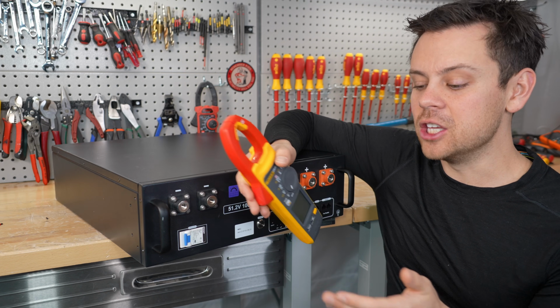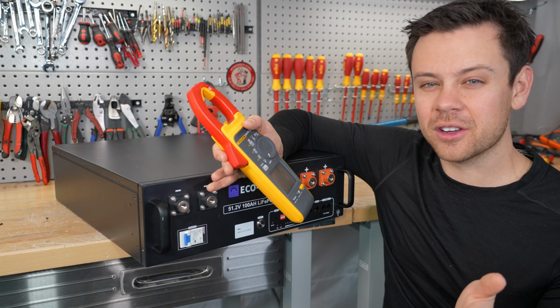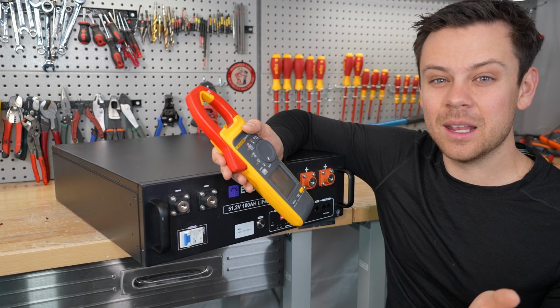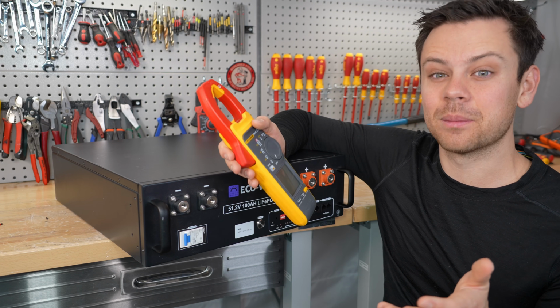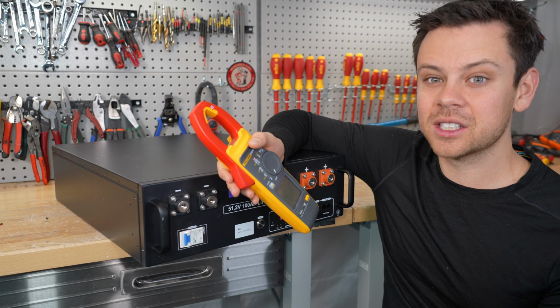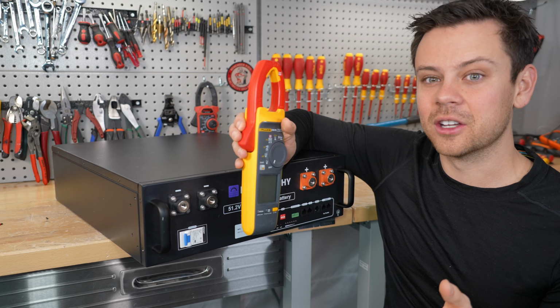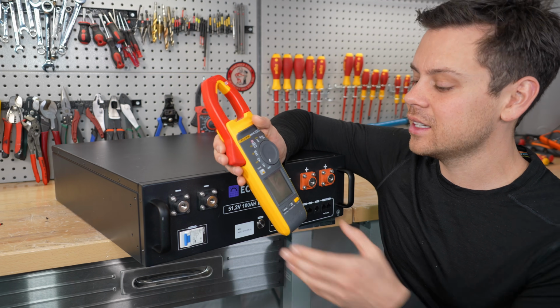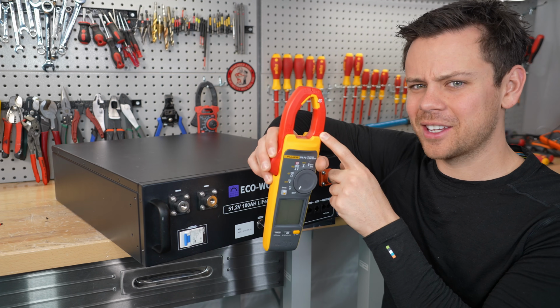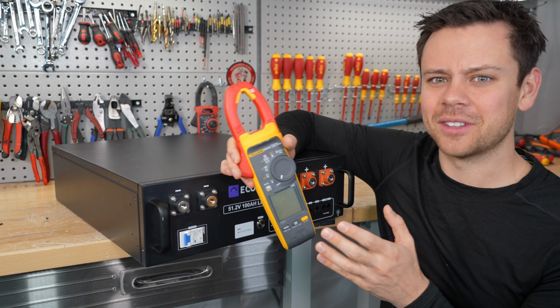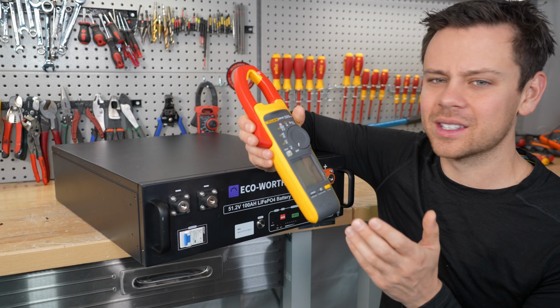Those heat up, you can't get them too hot. Even though it's a 500 amp shunt, you only want to use like 80% of its rated capacity, otherwise they get pretty hot, which changes the resistance value, and that changes how many coulombs it thinks there is. Even if this is like 1 or 2% accurate, I still get 0.1 to 0.5% accuracy. They all give me the same numbers.